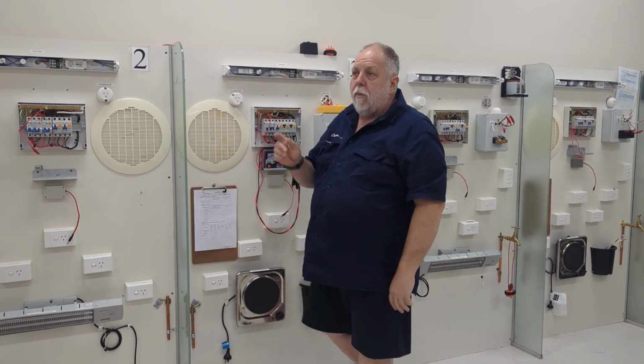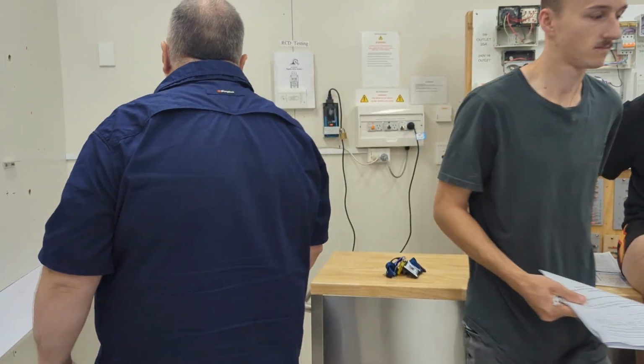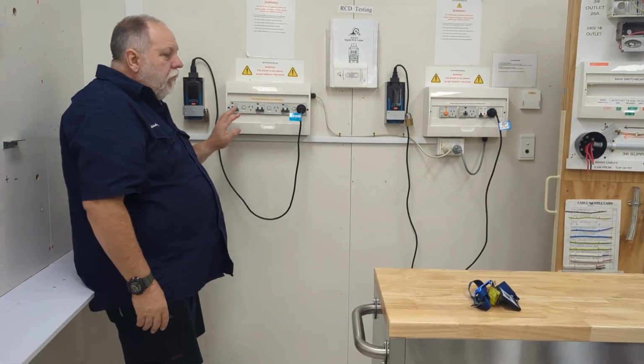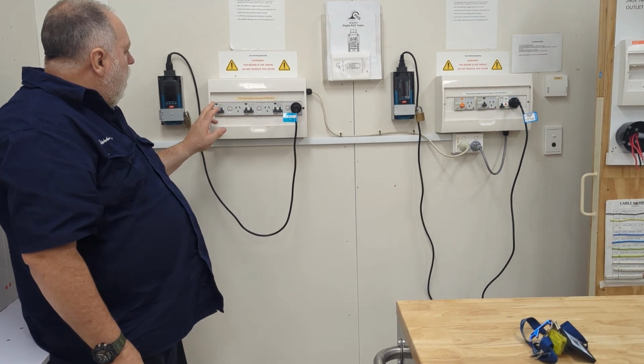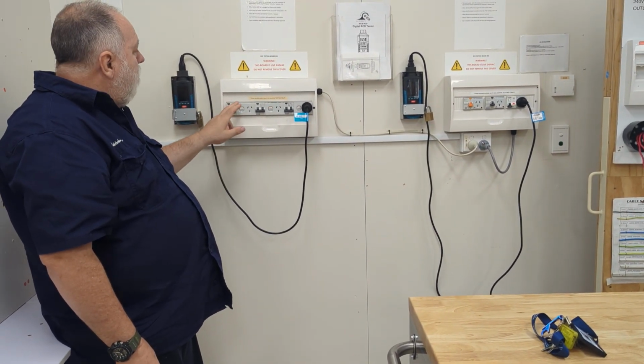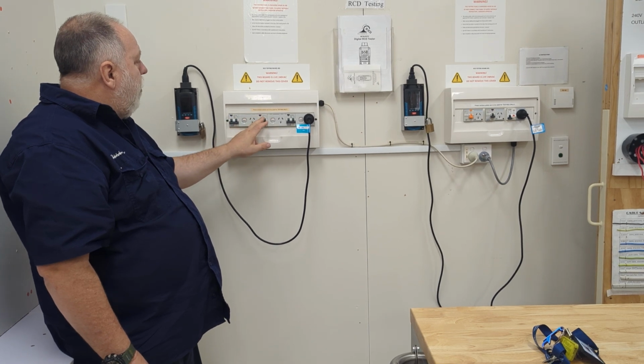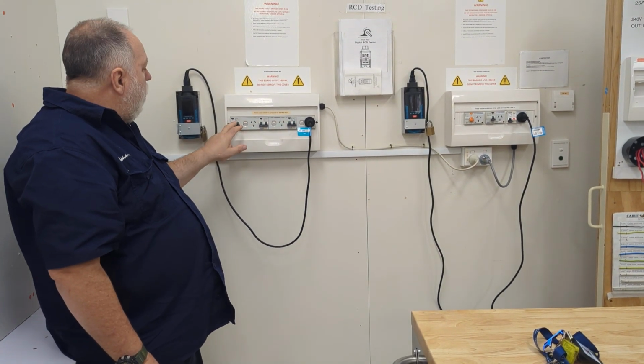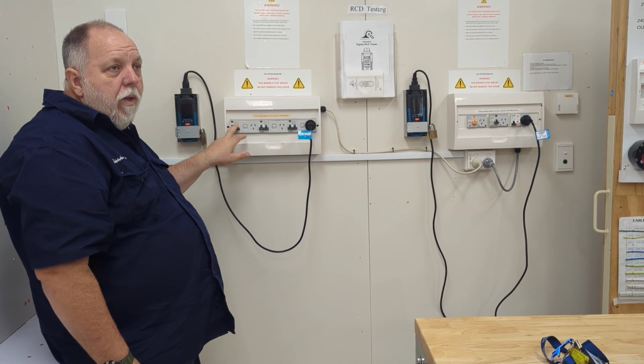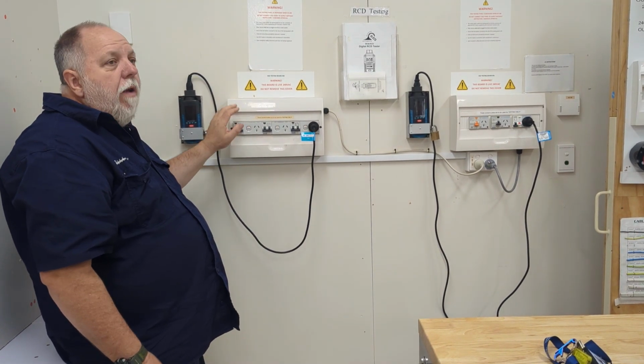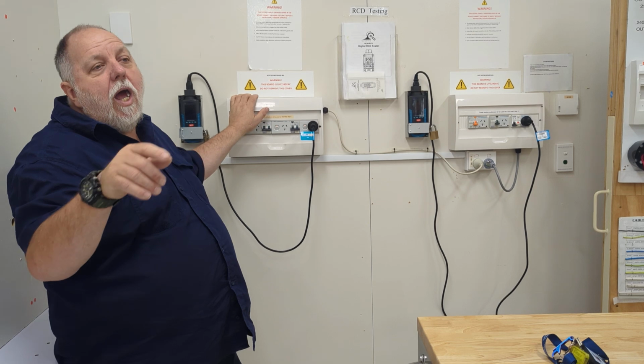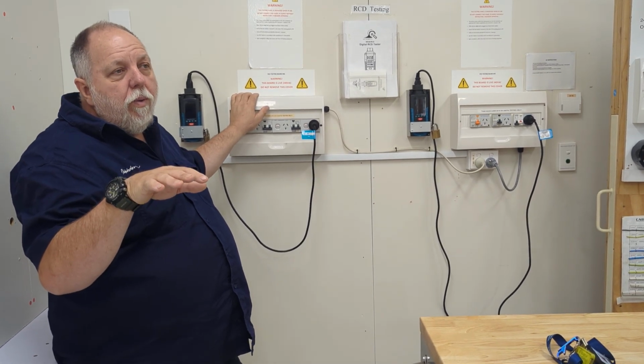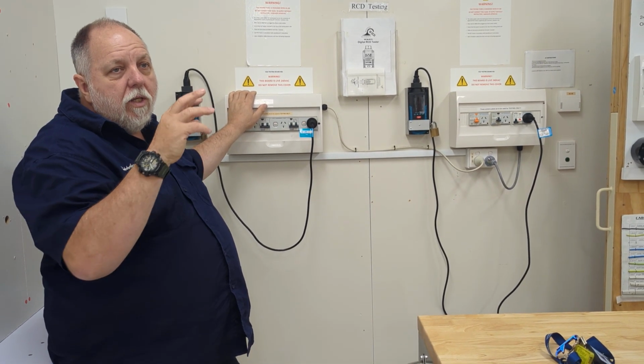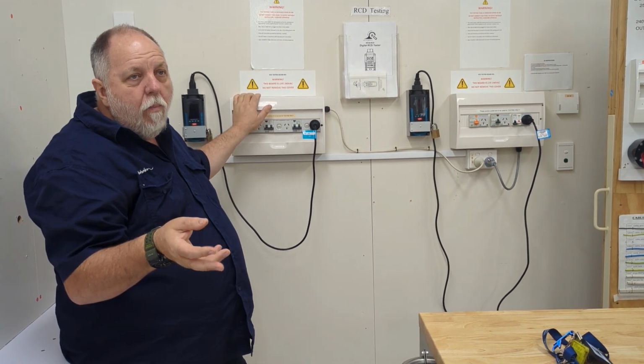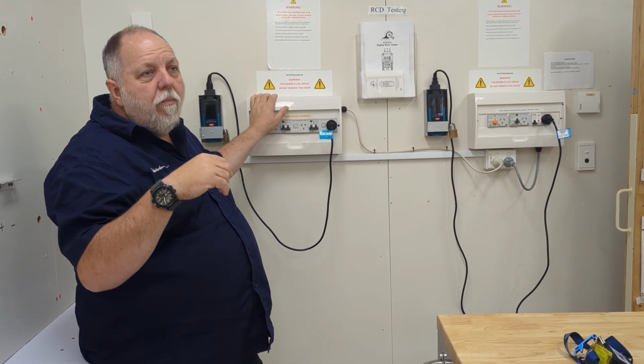All right. Let's come over to the RCD testing. RCD testing. I haven't got my glasses here, so I'm a little bit blind, but you have 3 RCDs. One will be 10, 30 and 100. But you need to be able to read the information off on the RCD. Normally you'll have C20-6KA. That has nothing to do with the fault loop, the RCD trip value. That's the current value and what we call a KA rating. Usually underneath it'll then say 10 milliamp, 30 milliamp or 100.